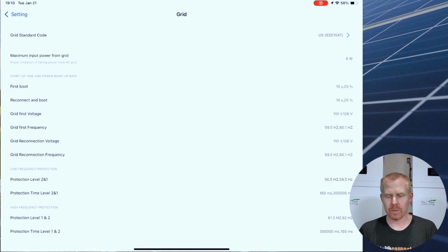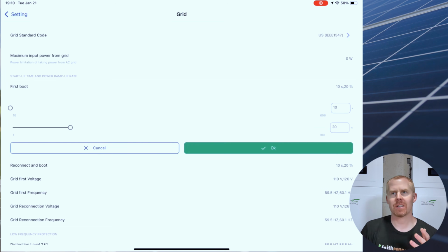The first boot and reconnect boot, I want to say by default, this is set to 300 seconds, which is like 5 minutes. So when you first press the button on the side of the inverter and tell it to start inverting power, it has to go through this countdown. Basically, it's a safety check window required by utilities for grid connected inverters. Well, 5 minutes takes an awful long time.